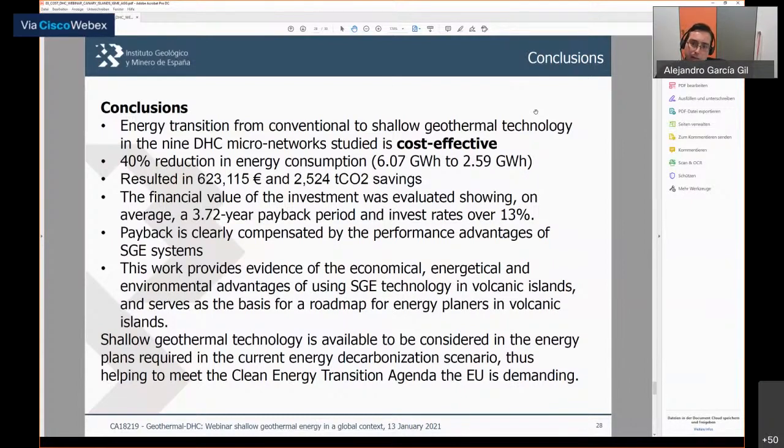And the coefficient of performance shows that those geothermal energy systems are about 4 times more efficient than conventional systems that use air to water heat pumps, air condensed liquid chillers, cooling towers, and gas boilers.